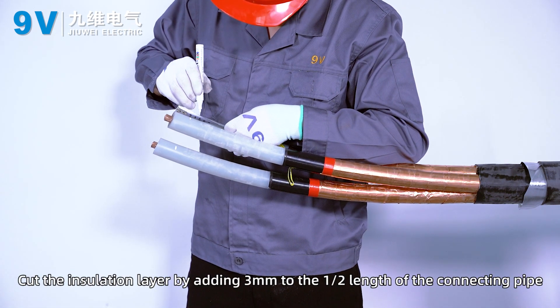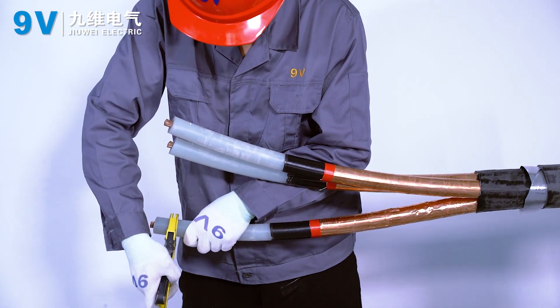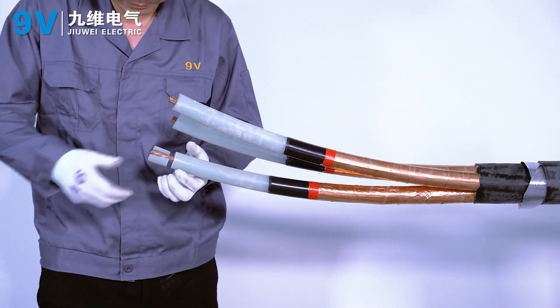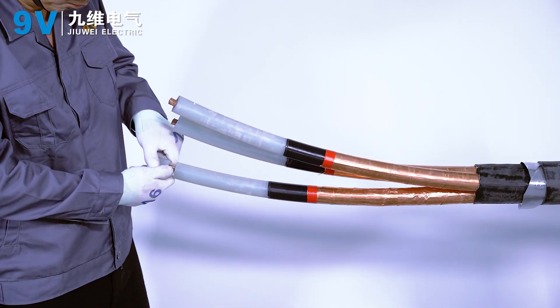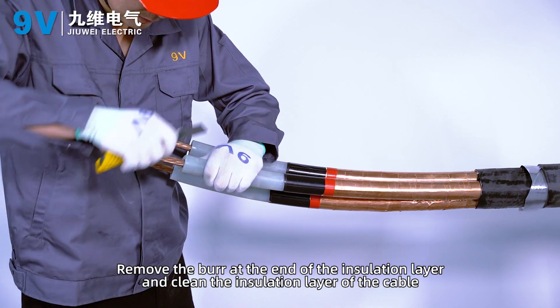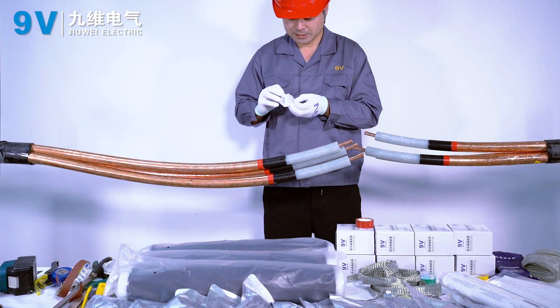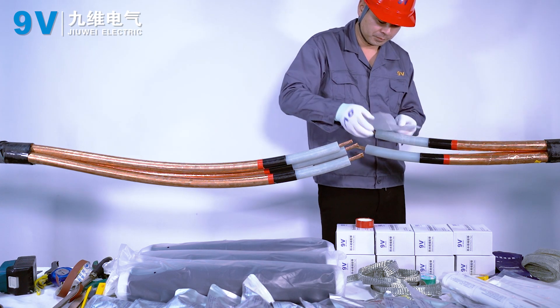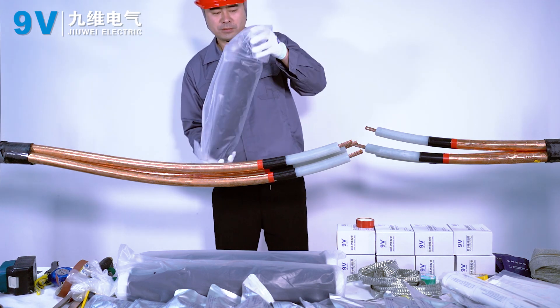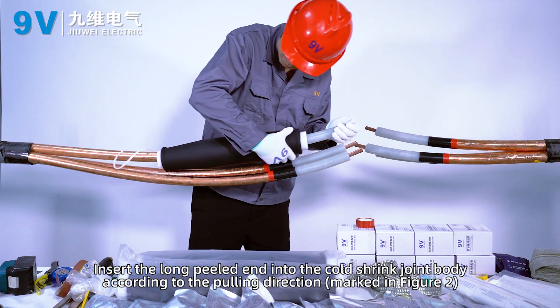Cut the insulation layer by adding 3 millimeters to the 1/2 length of the connecting pipe. Remove the burr at the end of the insulation layer and clean the insulation layer off the cable. Insert the long peeled end into the cold shrink joint body according to the pulling direction marked in Figure 2.